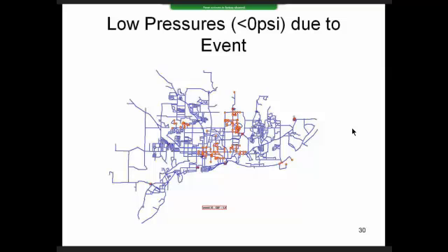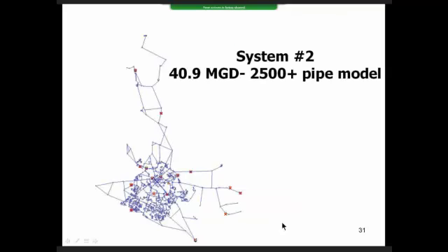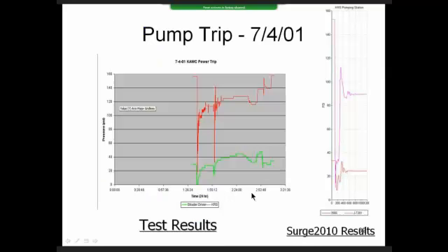We did another study, and this happened to be Lexington, Kentucky, where I was teaching at the university. And again, they have a pump station down here by the river. They had only one recording device over in this area, but they recorded a power outage pump trip, and they had actually recording at the pump station and in the system.